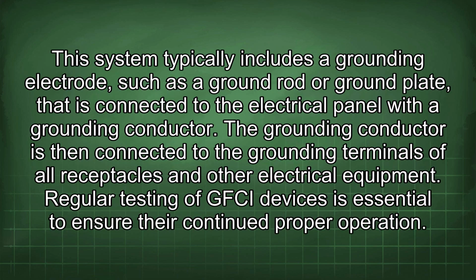This system typically includes a grounding electrode, such as a ground rod or ground plate, that is connected to the electrical panel with a grounding conductor. The grounding conductor is then connected to the grounding terminals of all receptacles and other electrical equipment.